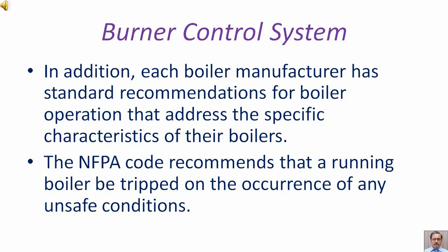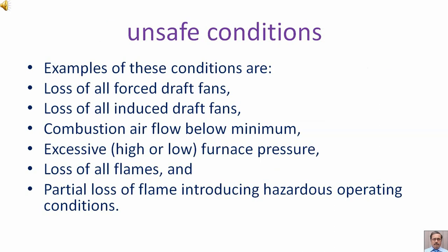recommends that a running boiler be tripped on the occurrence of any unsafe conditions. Unsafe conditions. Examples of these conditions are loss of all forced draft fans, loss of all induced draft fans, combustion airflow below minimum, excessive high or low furnace pressure, loss of all flames, and partial loss of flame, introducing hazardous operating conditions.